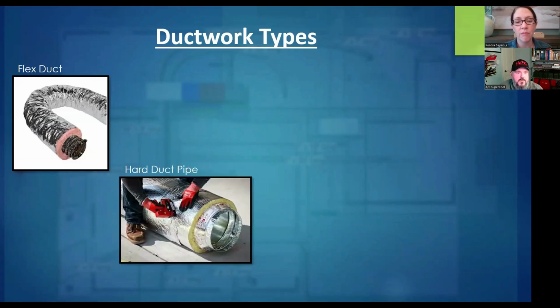Second is hard duct. This is my preferred method. It's rigid, insulated on the outside, leaving a smooth bare metal surface on the inside of the airstream. Given the smooth metal surface, it's the easiest and most effective choice for cleaning. But really, we shouldn't have to clean the system at all—we shouldn't get contaminants in it to begin with. If we have contamination in our system, that's a deficiency, and we need to figure out what's causing it.